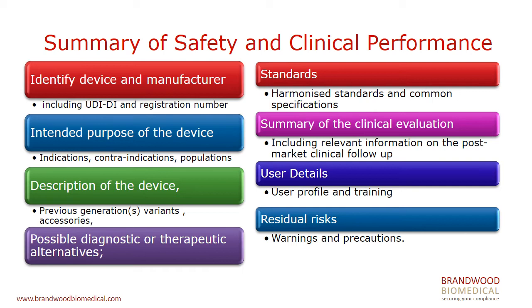And then finally, you must document the residual risks and the warnings and precautions that must be taken against the risks that couldn't be designed out of the device. So that's a summary of safety and clinical performance. It's something that needs to be produced and then kept current.